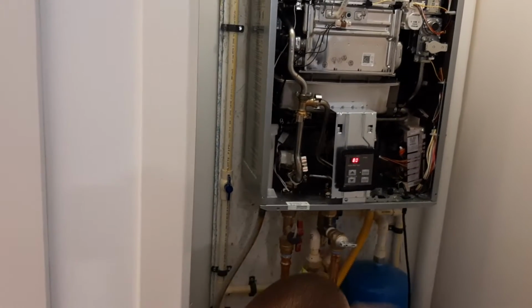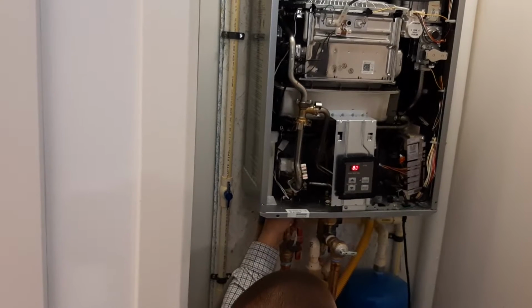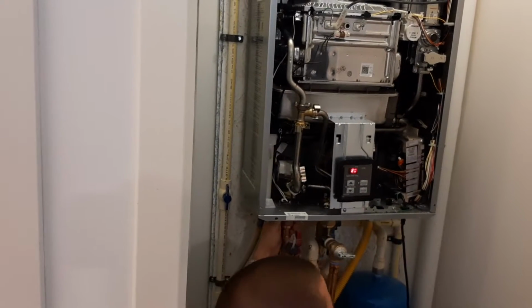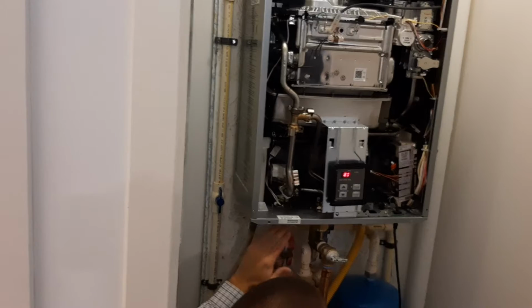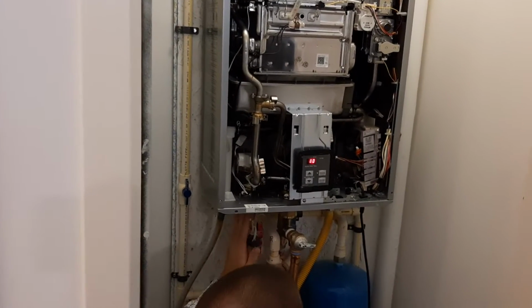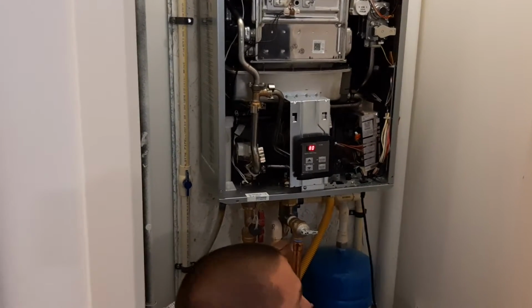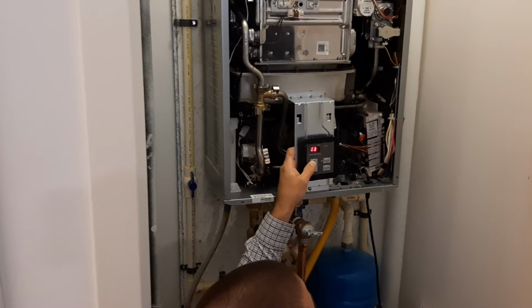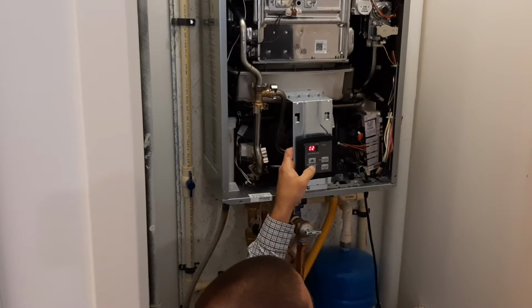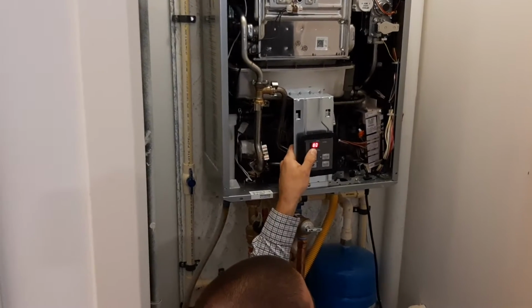A lot of times if this says 80, I can also grab right under here and check, does that feel like 80 degrees? Just to know if it's not hot here and we have an issue, or if it's something to do with the mixing valve. You can scroll through a lot of these status codes, but 1 and 2 are the most common: what's my current water flow and what's my outgoing temperature?